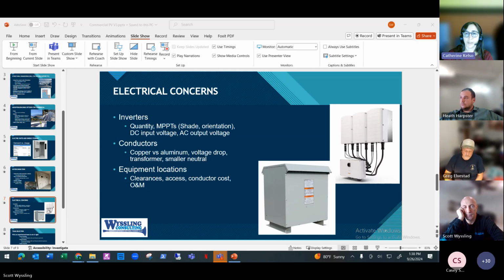Another thing with the conductors that a lot of contractors don't realize, if they're not used to working with three-phase, is the inverters are balanced systems. So the neutral conductor is only for reference, which means you can put in a smaller one. In some cases, you can skip the neutral conductor entirely. So that can also save you a lot of money if you're aware of that difference.